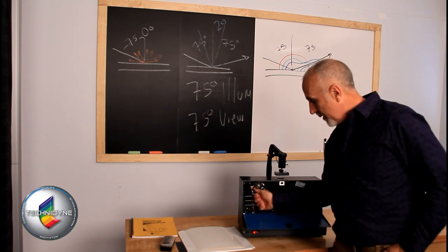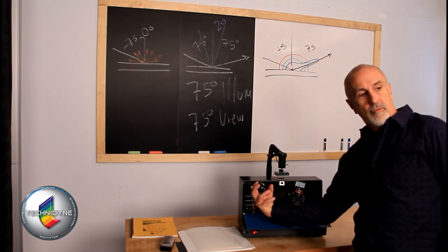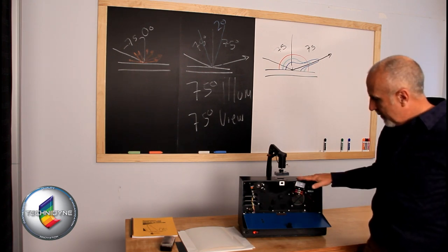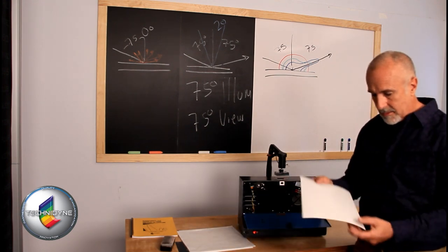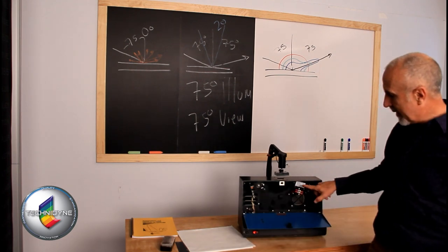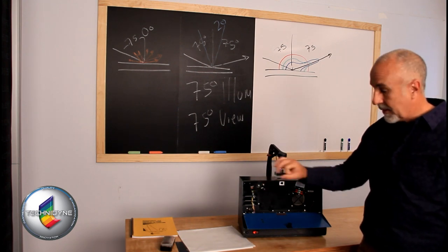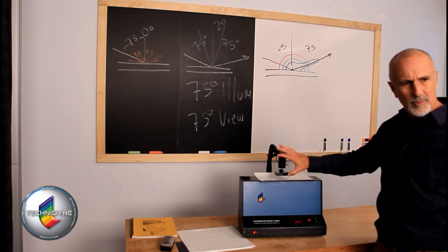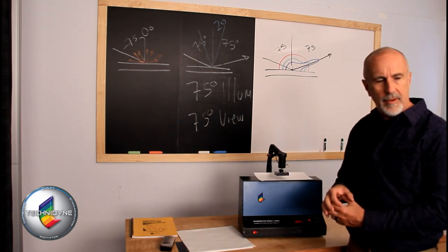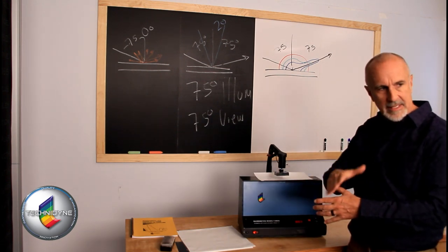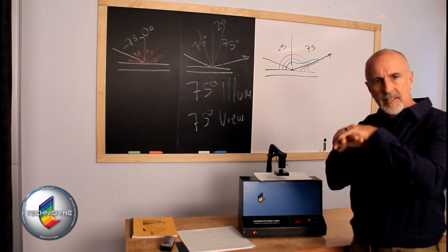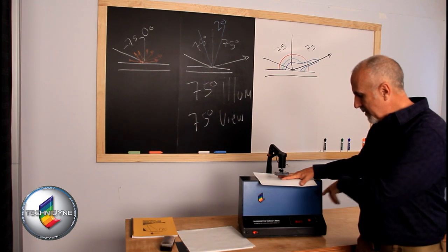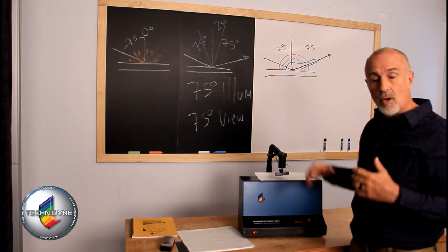So, again, our instrument is set up where we've got a photocell sitting here and it's looking for light energy being reflected off the sample which sits here and illuminated by a lamp that sits there. So, if a sample has a lot of glossiness to it, so like this instrument manual back cover, we would expect a lot of the light that strikes this to go back to the photocell. And so, again, that photocell is set with a proper aperture. So, you would load your sample on there. Now, this one actually has a vacuum hold down, because the sample opening on the gloss meter is fairly large. And when it's top loaded like this, you want to eliminate any sag into that aperture. So, this vacuum hold down pulls a vacuum on that sample so it sits flat on that. I don't have a vacuum pump for that right now, so we're just going to estimate these values just for illustration. So, this has a gloss reading of around 93 or so.